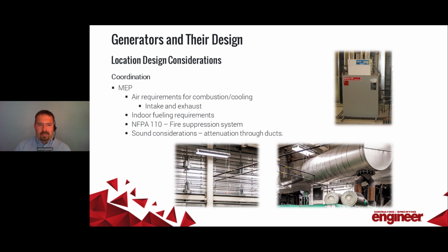The fire suppression system. Again, NFPA 110 kind of dictates what that has to be. They prohibit the use of a CO2 system or an automatic dry chemical system. There are some exceptions, but generally that system is a wet system in the generator room. And then also, again, sound consideration, attenuation through the exhaust ducts in and out of the room. Maybe there's some consideration to adding some baffles or something to that element as well.